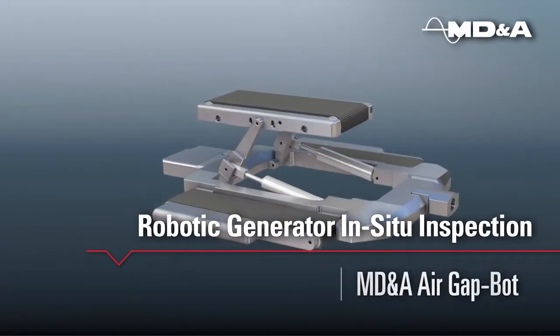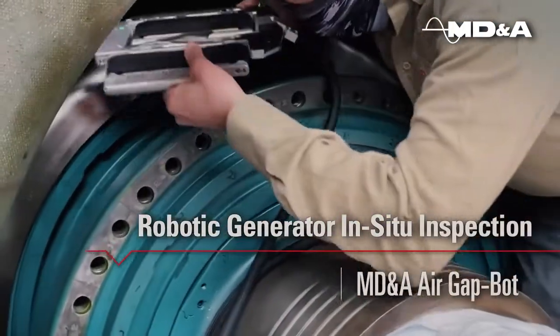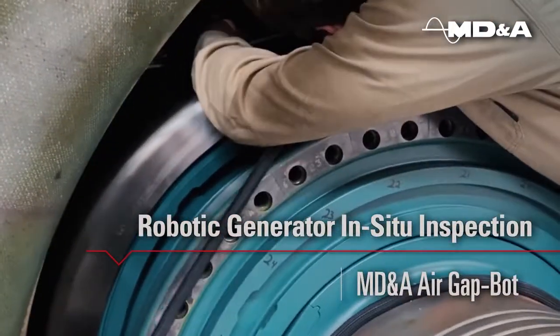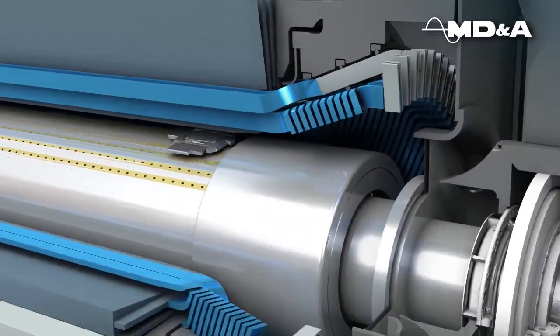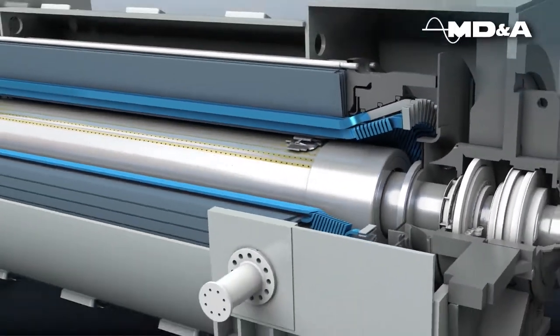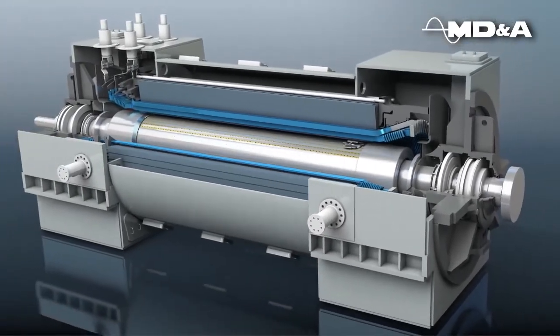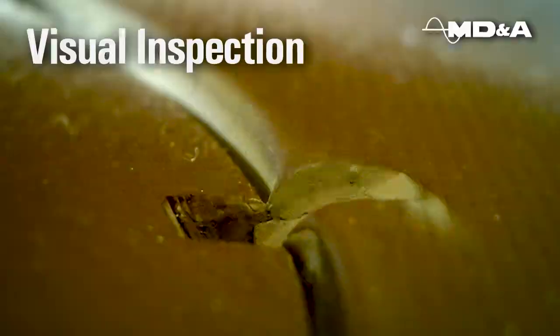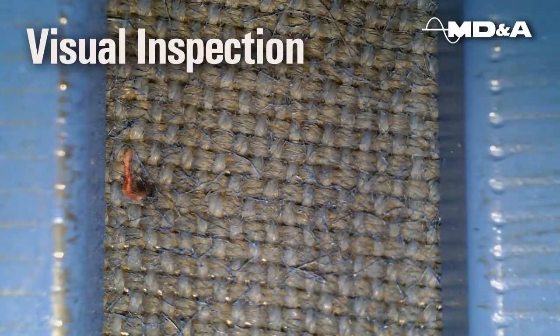MD&A's Air GapBot can perform full generator inspections without removing the field. This robotic generator inspection crawler can be used on generators with entrance gaps as narrow as 0.9 inches or 22.86 millimeters. MD&A can provide the customer with time and location stamped high-definition video and still images.